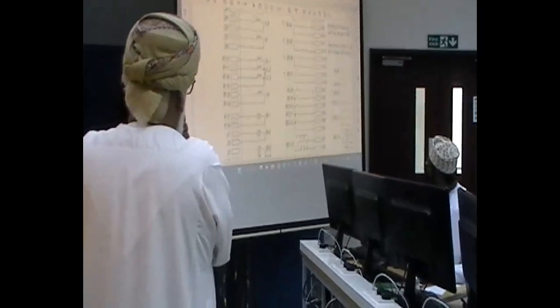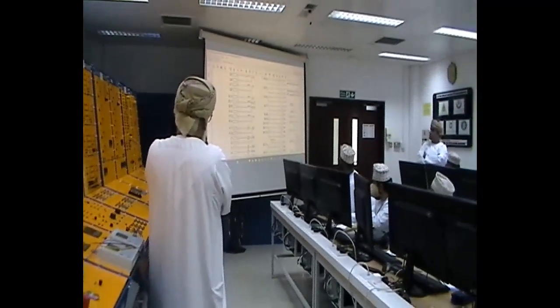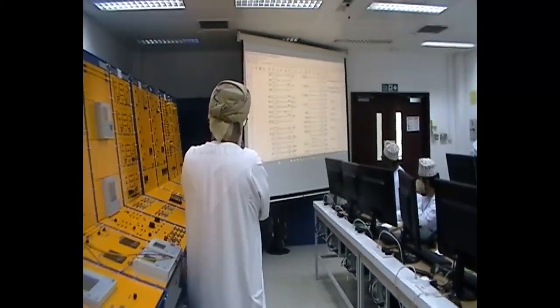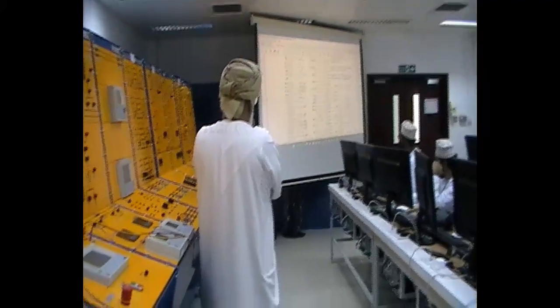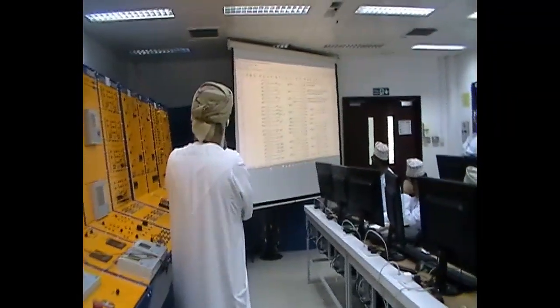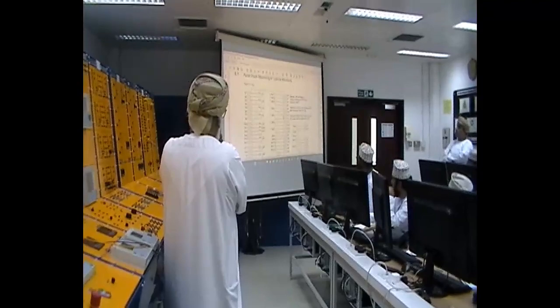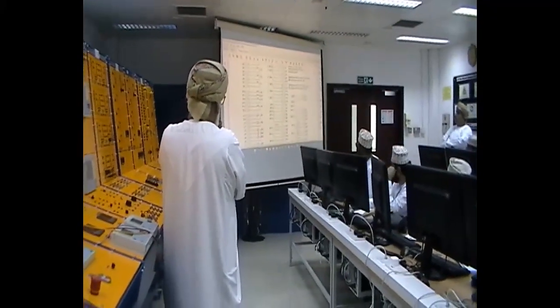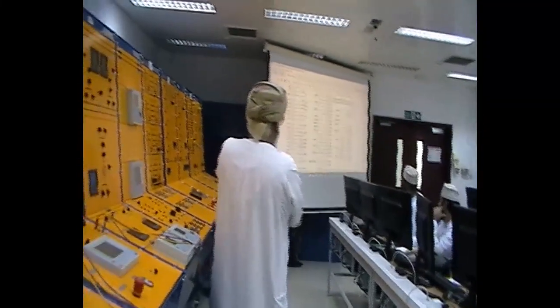Usually the current comes from the CT in the substation. The VT connection is in the R card, R card 15, 17, whatever. Now, before this, I have to locate the auxiliary supply to just make the relay on. So usually it's in the K card, and it is.